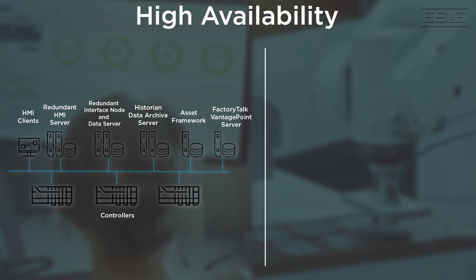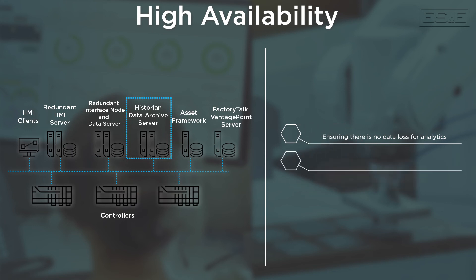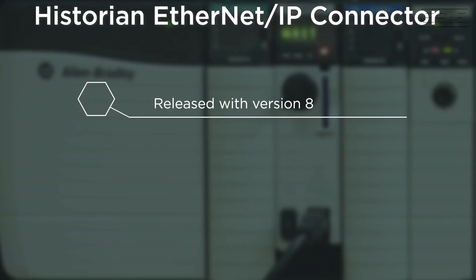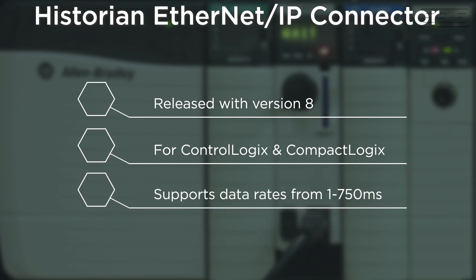We can also take this a step further — not only having redundant interface nodes and redundant data servers, but also redundant historian data archive servers. With redundant interface nodes, we ensure data is not lost and will eventually be available for analytics. With high availability architectures — such as redundant historian data archive servers — we ensure you always have visibility of that data. With version 8 of Historian SE, we've released a new data connector for use with ControlLogix and CompactLogix controllers, supporting data rates of one millisecond to 750-millisecond collection time — a very powerful addition for high-speed data collection applications.